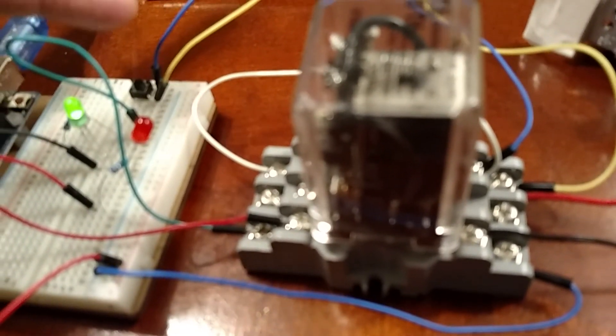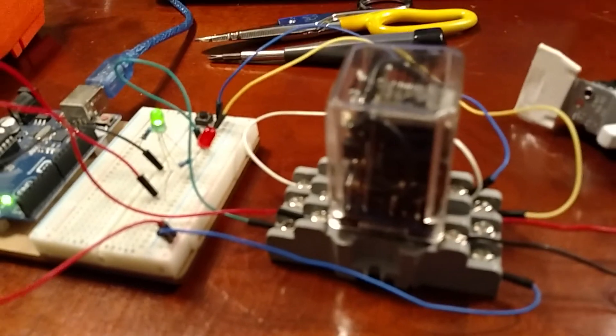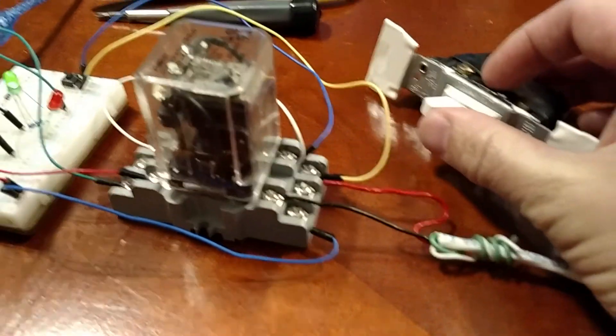When we press the start button, the relay changes state. When we release the start button, the relay is latched and it will stay that way in its energized state until we press the stop button.